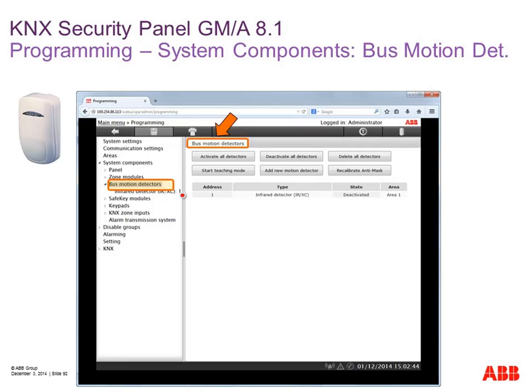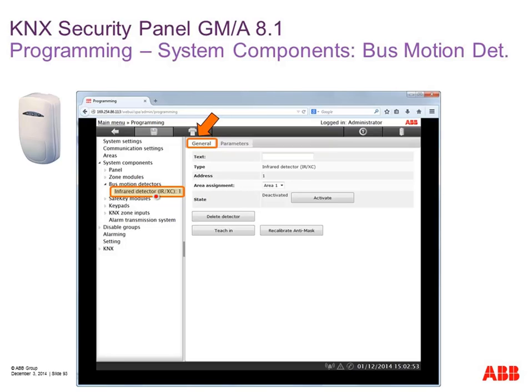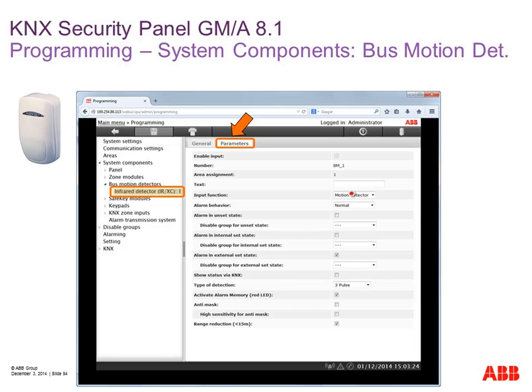By closing the housing, the tamper contact is pressed down — this is the step to teach in the motion detector. When you close the housing, the panel recognizes it as a new motion detector and automatically assigns address number one. You can change the address later or add detectors manually. After teaching in, you see the motion detector with address one, type infrared motion detector for class C — the highest security level — still deactivated. Click on it, write the name or room where it's installed, and configure parameters: type, alarm behavior (pre-alarm or access type), alarm memory LED, anti-mask, and other specific parameters.